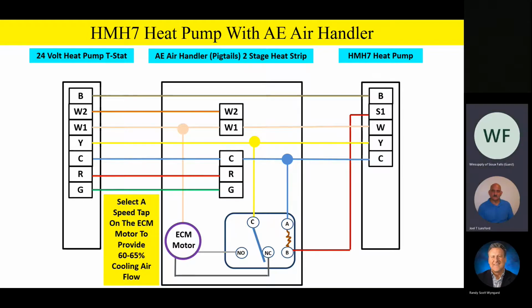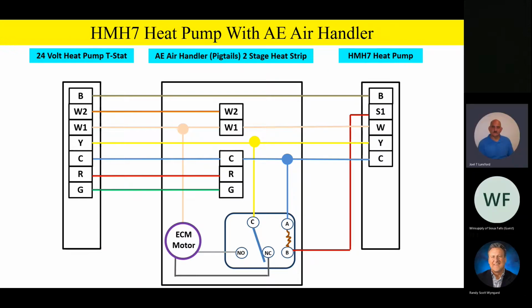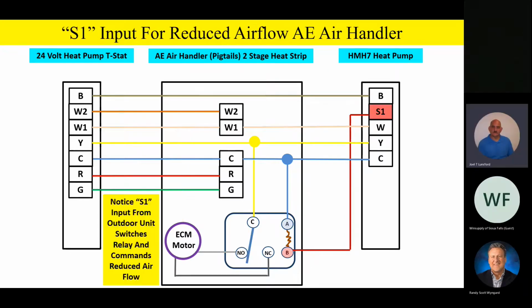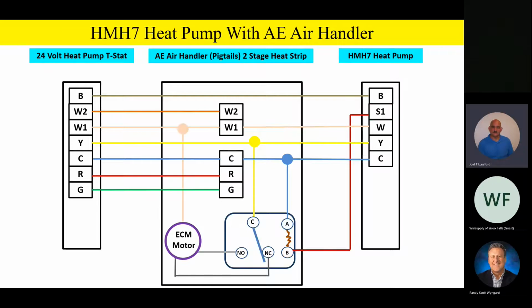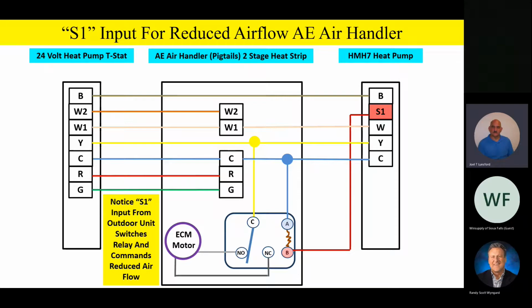Okay, well, fantastic. So let's go ahead and do a little animation. Watch the PowerPoint closely. You'll notice that when we energize that S1 terminal, we're going to switch that relay. Let me go back and do it one more time for you. So when the outdoor unit is saying, hey, give me reduced capacity, I'm at a lower point of modulation, bang, it's going to go ahead and energize S1. It'll switch that relay, and we're going to drive that indoor fan to that 60% airflow by way of that relay.